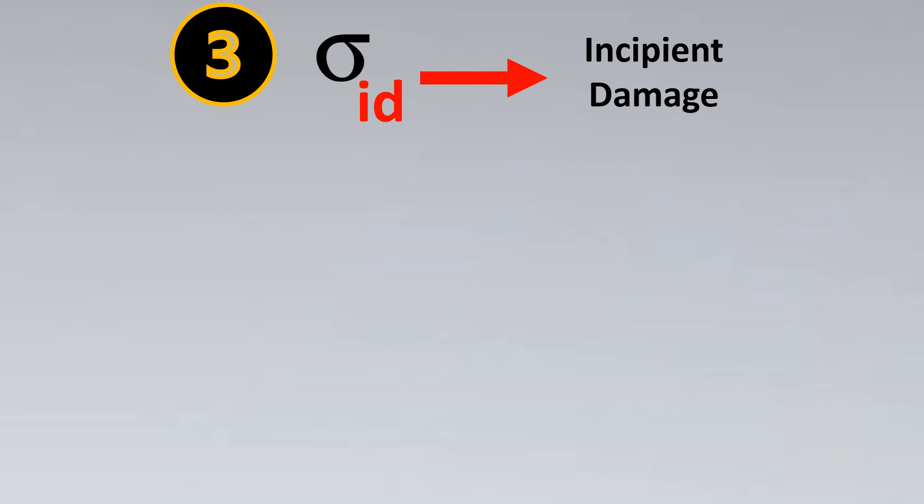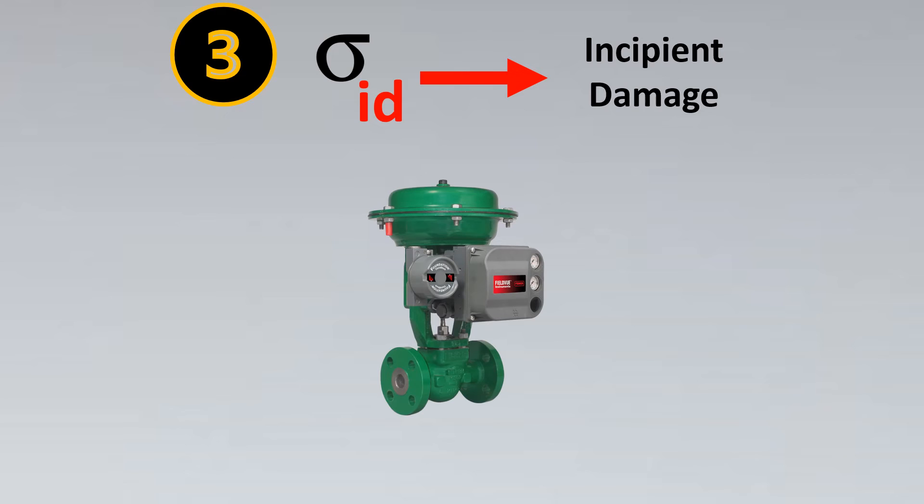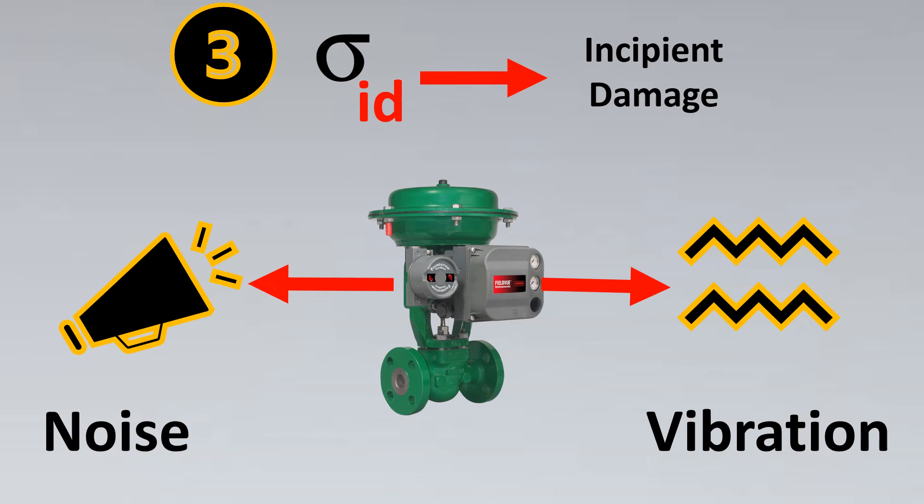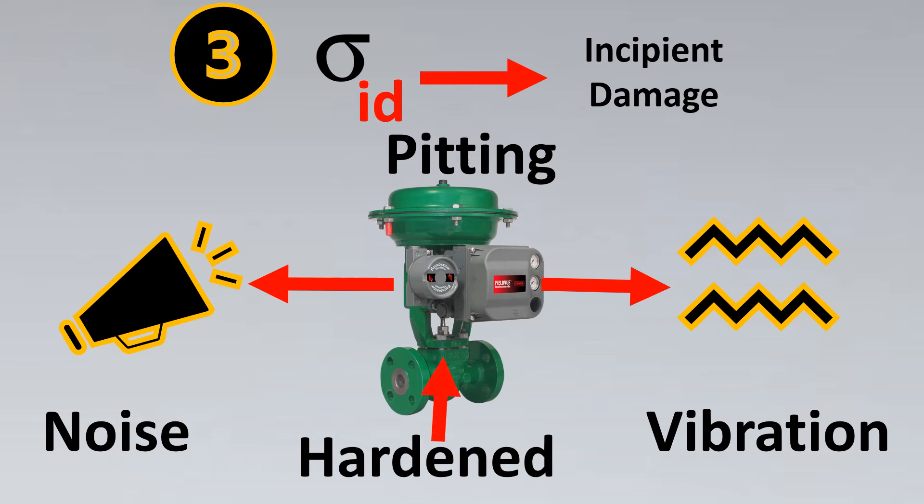Now let's look into the third term, which is ID. Here is where you need to get more serious and take more precaution because ID stands for incipient damage. This incipient word means start, so this is the start of damage to the valve. Your valve can get damaged - the vibrations are present and the noise is present and the level is high. For such cases, there are chances of pitting, and you have to use some special precautions like hardening the trim material of the valve, otherwise your valve might not be able to sustain and would get damaged.